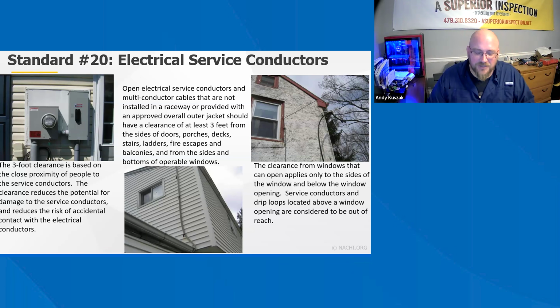For me, I have an extension pole that I use for roofs that I put my camera on, and I have marked distances on it. And so I stay a safe distance away. If I'm ever curious about the distance from the electrical service conductor, I will take that pole and, like I said, stay a safe distance away so that the pole can't fall on the line. Then you can use those extension poles and the marked distances to figure out how high that service drop is, or at its lowest point, how high it is.